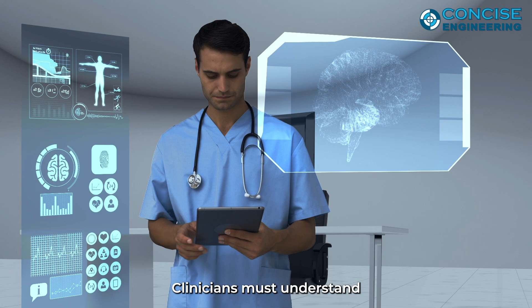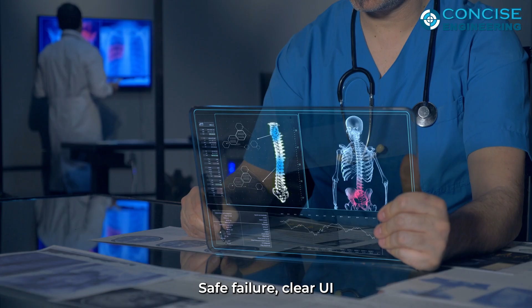When things go wrong, explainability matters. Clinicians must understand when confidence is low, when outputs are unreliable, and when manual review is required. SAMD must communicate uncertainty clearly, provide safe fallback behavior, and avoid silently degrading into dangerous recommendations. Safe failure, clear UI messaging, confidence thresholds, and traceable logic are essential parts of any SAMD evidence strategy.